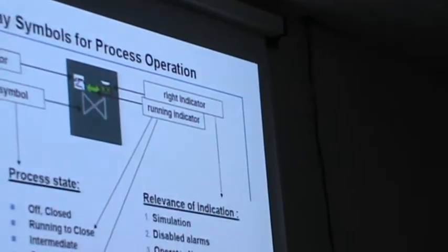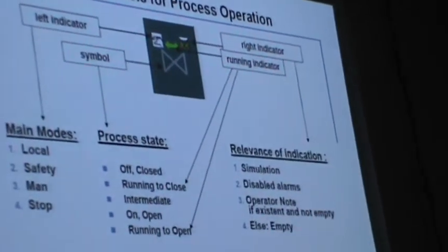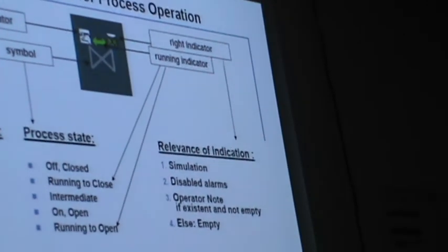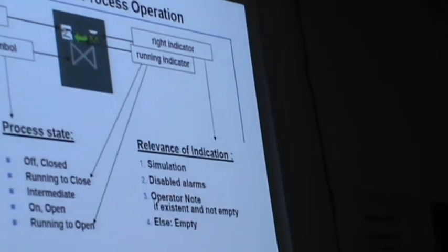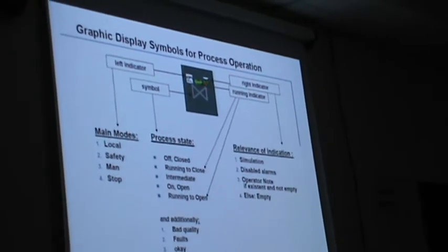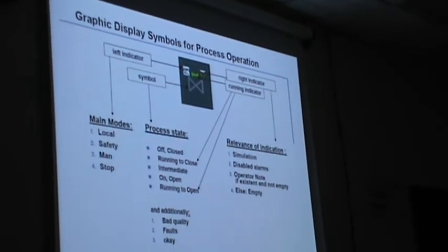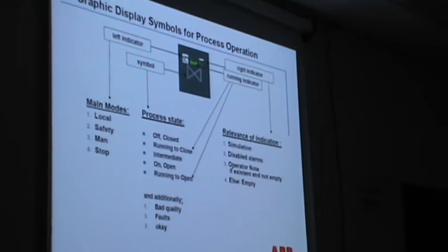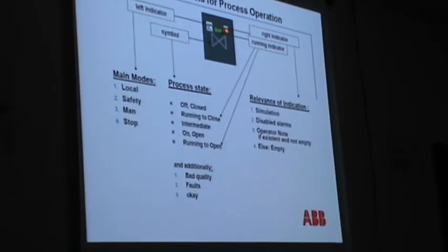Now for example, here I show you the alarm disable. Say some transmitter is malfunctioning and continuously updating in the alarm list, and we don't want this alarm. So you want to bypass that alarm, you want to block that alarm. The operator has the provision to do that. If you do it like this, you will get a symbol like this, so you can remember in the future, yes, we have blocked this alarm, we need to remove it. That kind of information will be available here.